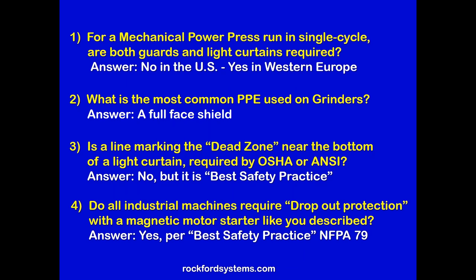Number two, what's the most common personal protective equipment used on grinders? Well, that's by far a full face shield. A full face shield, not just safety glasses, but for the last 20 years or so, most all plants I get into have a full face shield. Three, is a line marking the dead zone near the bottom edge of a light curtain required by OSHA or ANSI? Well, the answer is, it's the ANSI standard suggestion as a best practice to mark the dead zone so that you can verify that people are not reaching underneath the light curtain. Number four, do all industrial machines require dropout protection with a magnetic motor starter like the one described? According to best safety practice in NFPA 79, yes, they do. So replace your manual motor starters with magnetic to give you that anti-restart feature.